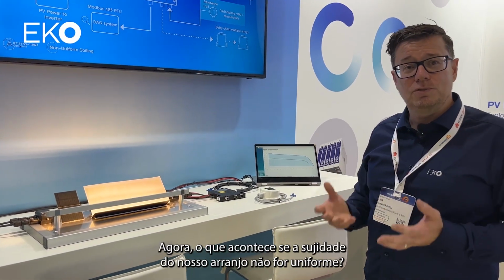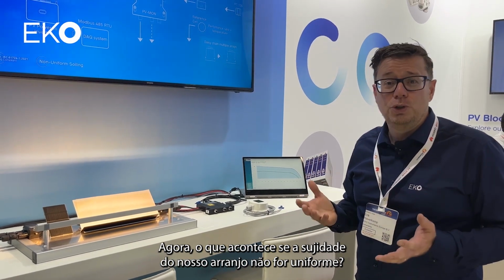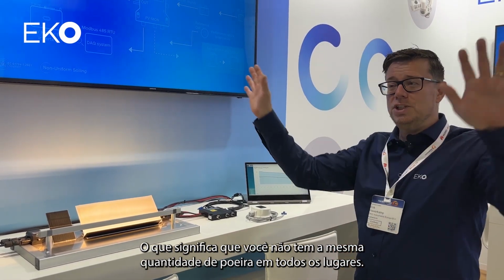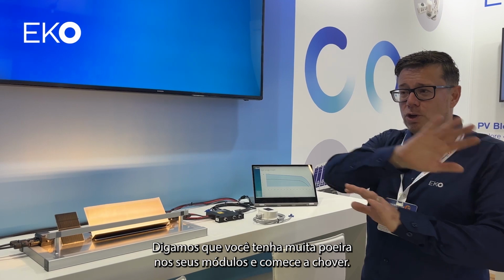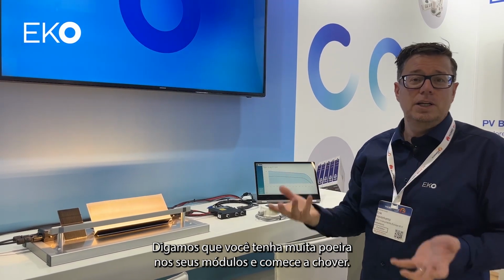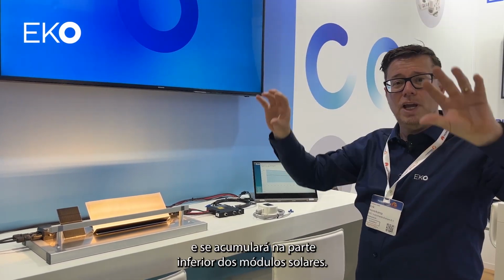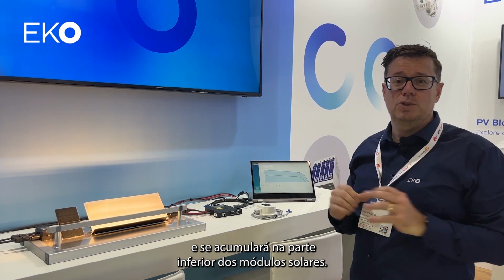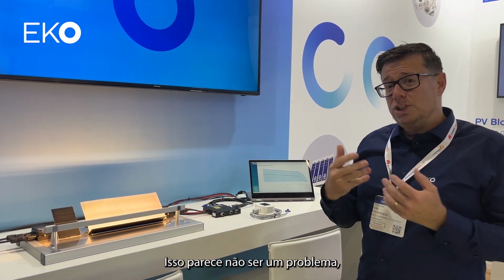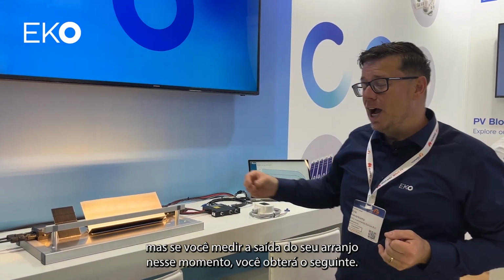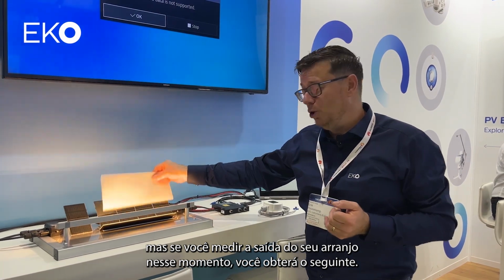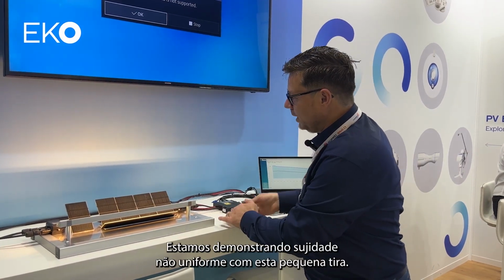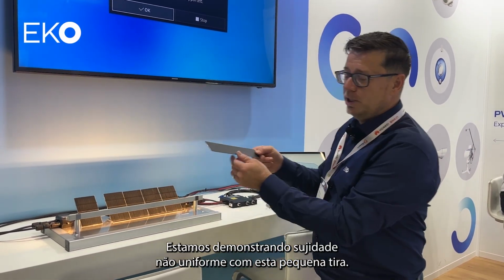Now what happens if the soiling of our array is non-uniform, which means you don't have the same dust everywhere? Let's say you have a lot of dust on your modules and rain is falling. Then the dust will go down and accumulate at the bottom of the solar modules. This sounds like no problem, but if you measure the output of your array at that moment, you will get the following. We are demonstrating non-uniform soiling by this little strip.